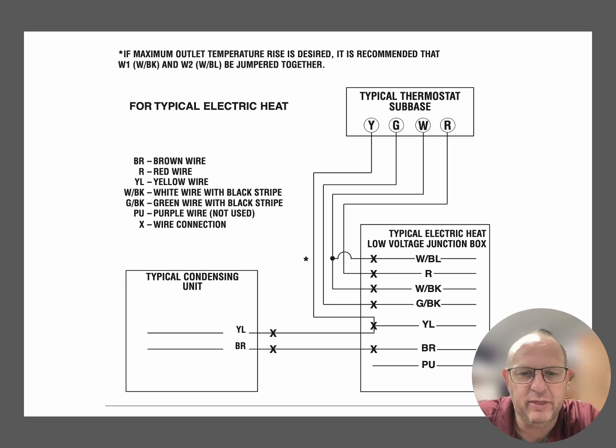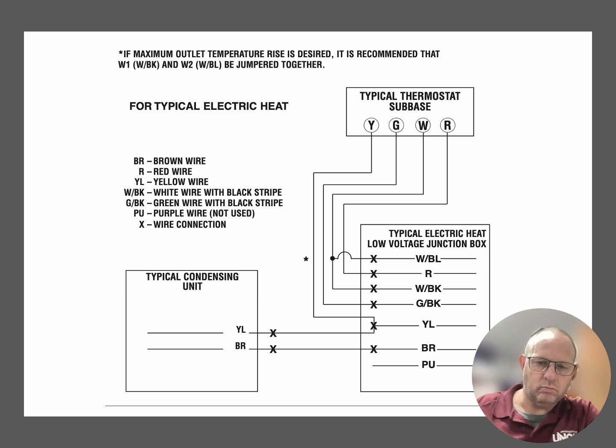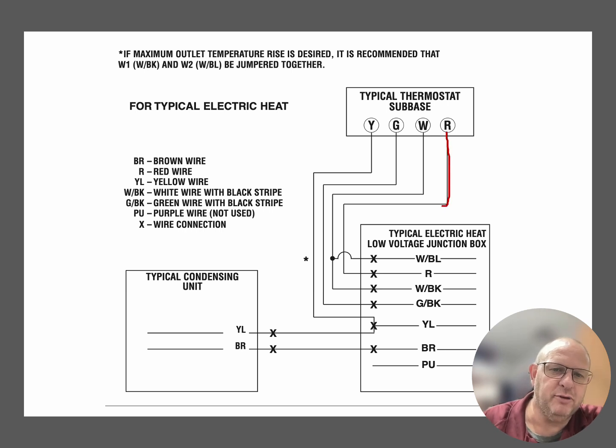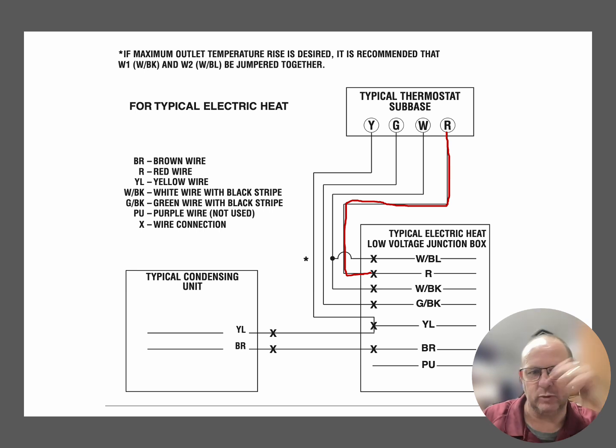So electric heat, this is the typical sub base that you will see on the indoor unit. You'll have the red wire. Red wire will run up to the thermostat, but that power is coming from that indoor unit, from the transformer that's a step-down transformer on the indoor unit. The white wire is going to be for the heating, but we're not in heating, so you guys just took that class.